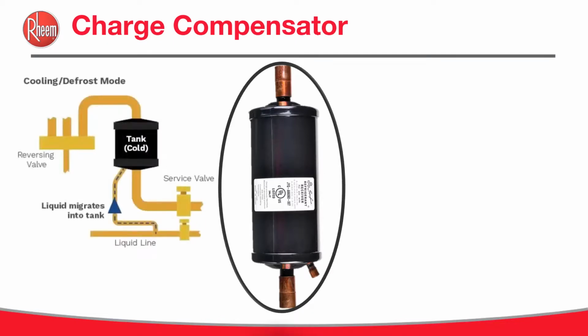Charge compensator may be installed in the vapor line between the indoor coil and the reversing valve. So here we have your reversing valve, and here's the tank. I'm going to go to your coil. It also has another line that hooks into your liquid line. So the compensator may be installed here.